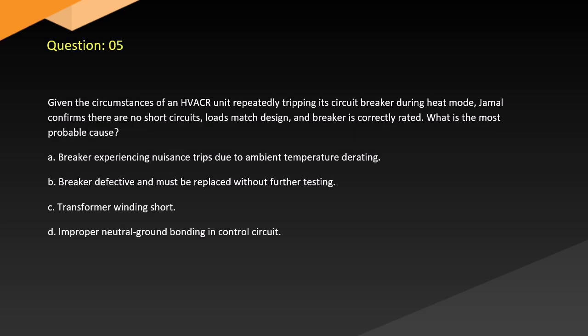Question 5. Given the circumstances of an HVAC unit repeatedly tripping its circuit breaker during heat mode, Jamal confirms there are no short circuits, loads match design, and the breaker is correctly rated. What is the most probable cause? A. Breaker experiencing nuisance trips due to ambient temperature derating. B. Breaker defective and must be replaced without further testing. C. Transformer winding short. D. Improper neutral ground bonding in control circuit.